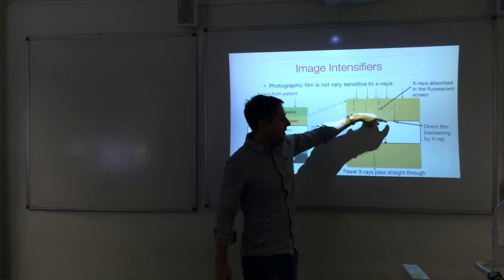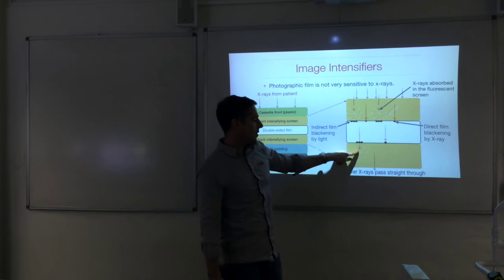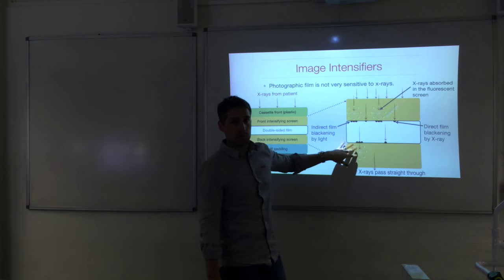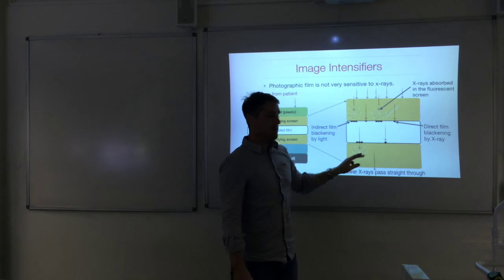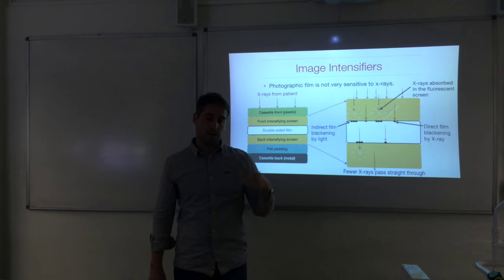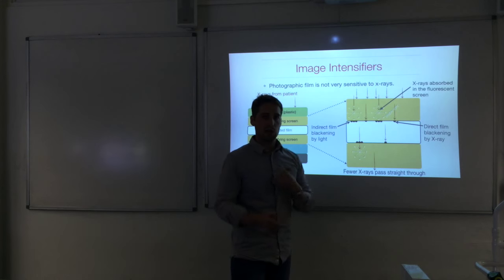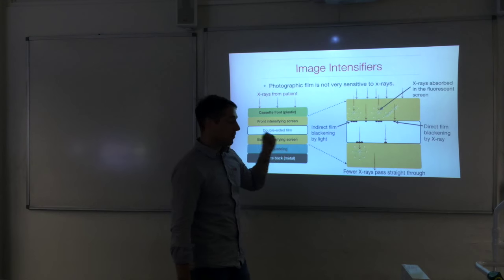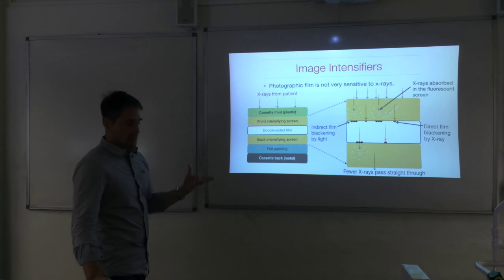There is also blackening on the rear of the photographic film from the screen behind it. Because x-ray photons are absorbed in the intensifying screens, fewer pass straight through without contributing anything. This is a double positive: we get many visible photons which darken the film more quickly, and there are fewer x-rays that pass through and do nothing. That's how image intensifiers work.